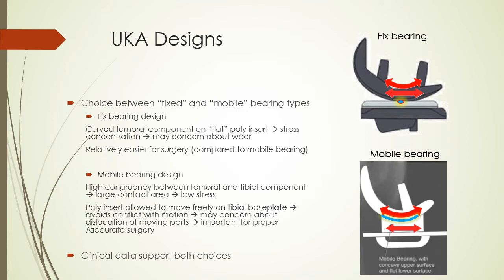But as you can see in the upper right figure, if you have a rounded femoral component on a flat surface, you may have point loading that causes stress concentration and may be a concern about poly wear.